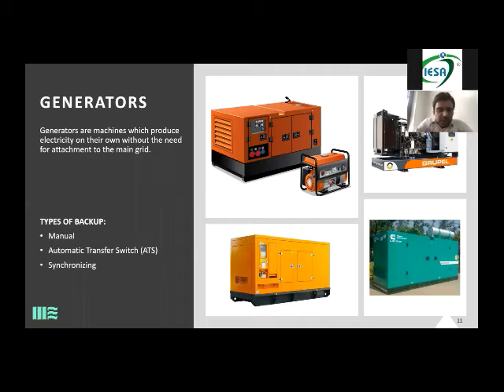Well, I have a question here. For example, we are distributing power for, let us say, 4,000 kilowatt, and it's an entire outdoor event. Is it possible to have backup for the entire 4,000 kilowatt? As soon as you start using synchronization, say you have 4,000 kilowatts of load and you take 500 kVAs and make a set out of it. Your 500 kVAs can give you a 60 or 70% output, which could be like 350 kilowatts.